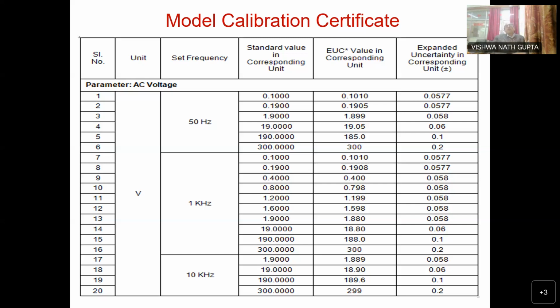Sir, once you rub our hand also, it generates some millivolts. That's why, in the field of calibration and electronics, our hands also should be earthed, so that any stray magnetic field or electric field does not pass on to the testing equipment. So whenever we are going to use it, we have to safeguard our area by any means, with proper earthing, especially in the high voltage area.